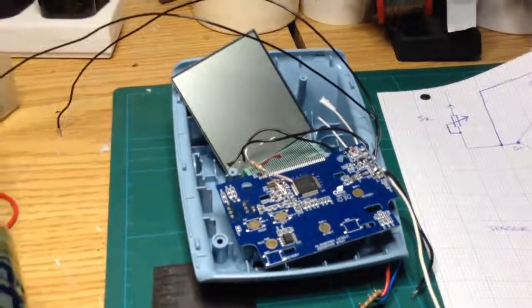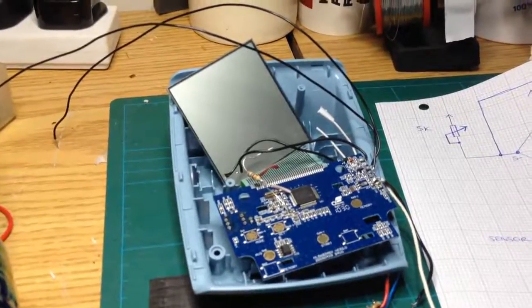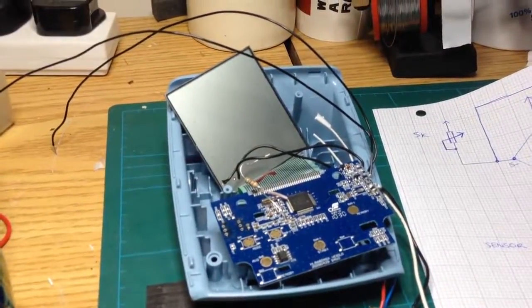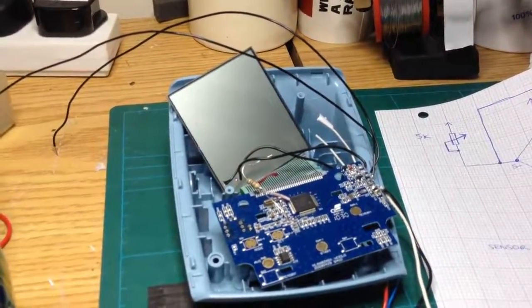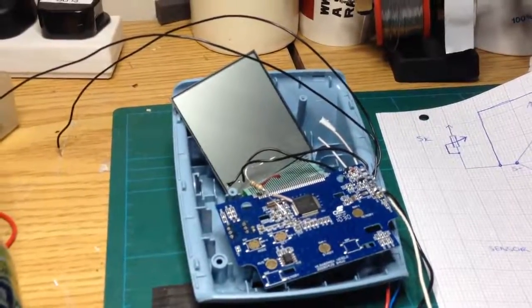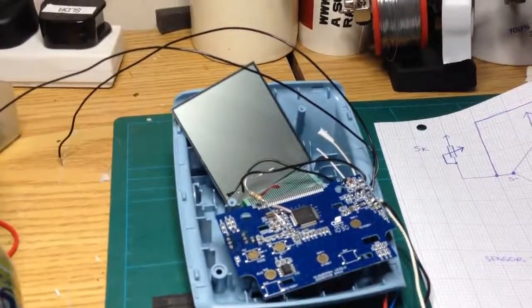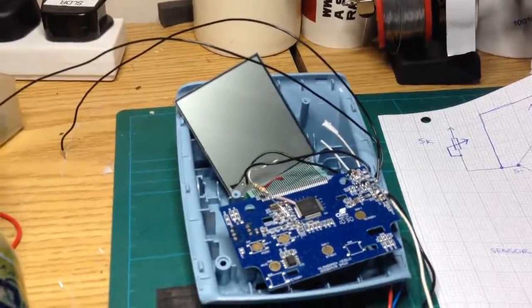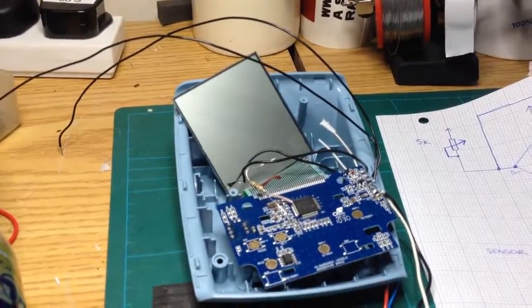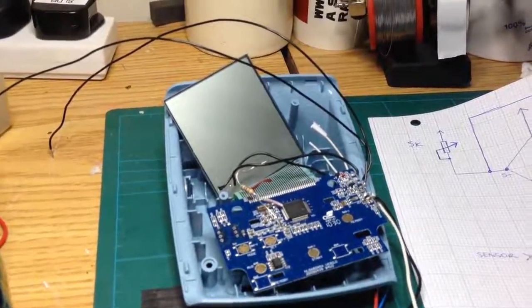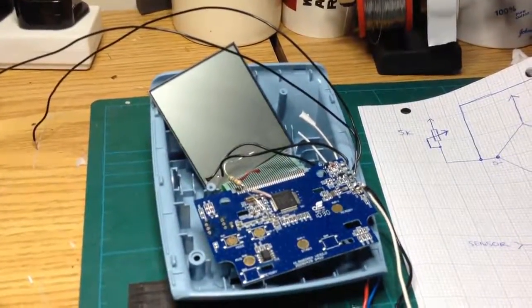The blood pressure monitor itself is basically just a processor which is hooked up to a compressor. That compressor then fills a reservoir, and that reservoir vents back into a pressure sensor, which works out the pressures, and they use the pressure sensor as well as some DSP to figure out when the systolic and diastolic pulse are happening during the measurement.